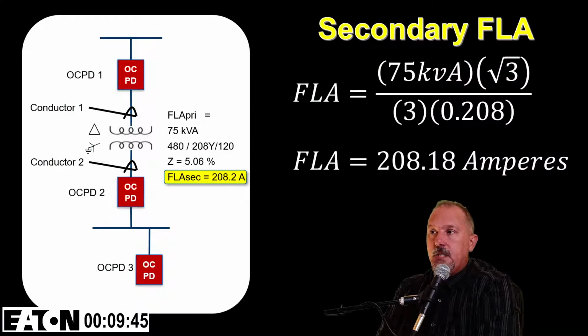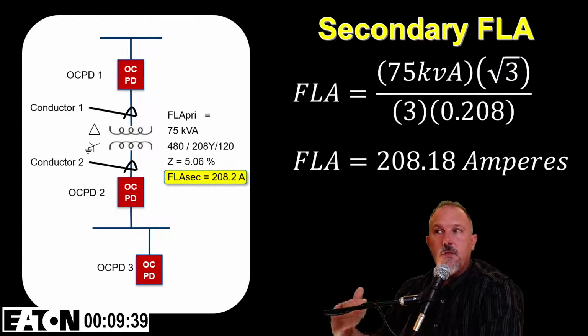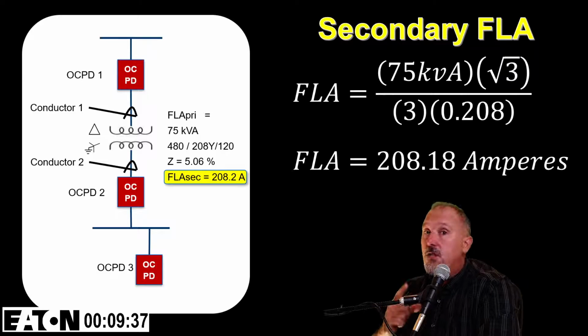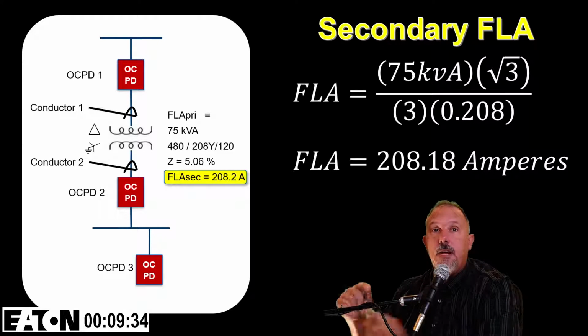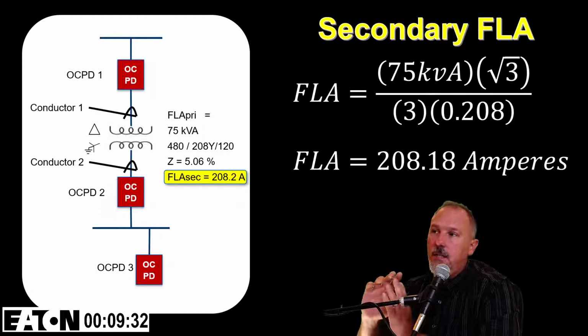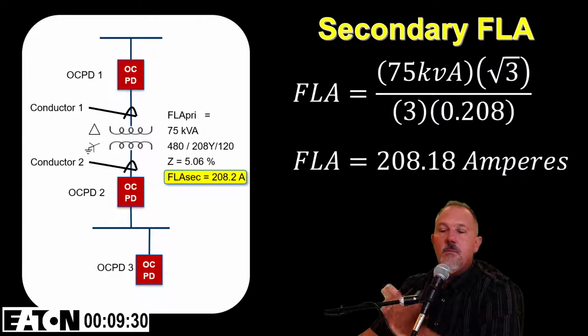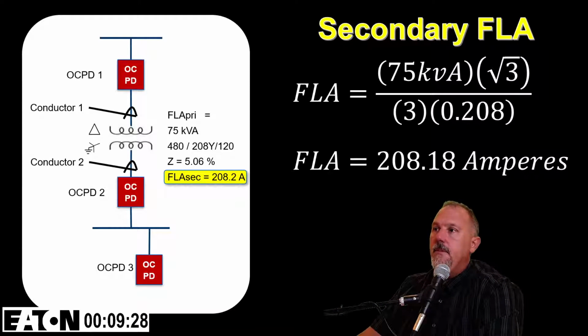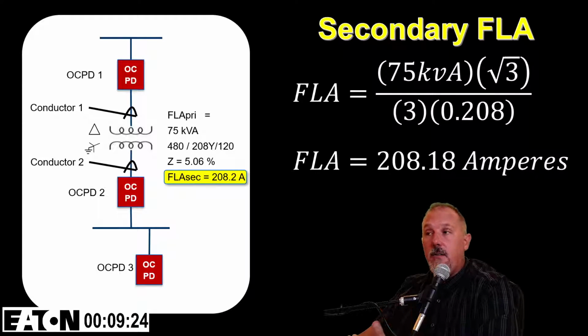secondary full load amps. On this transformer is 208.2 amps based upon 75 times the square root of 3 divided by 0.208, which is 208 volts divided by 1,000. So I just take care of that right off the bat, and it's 0.208 kV. And that's your line-to-line voltage. So my secondary current, full load amps, is 208.18.